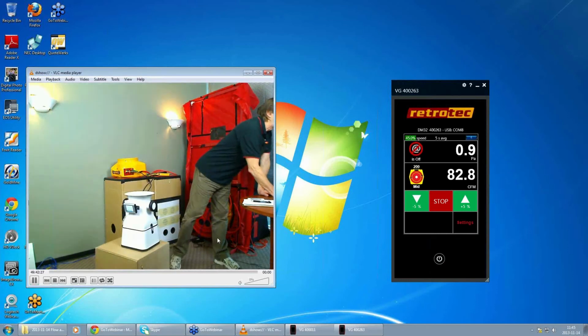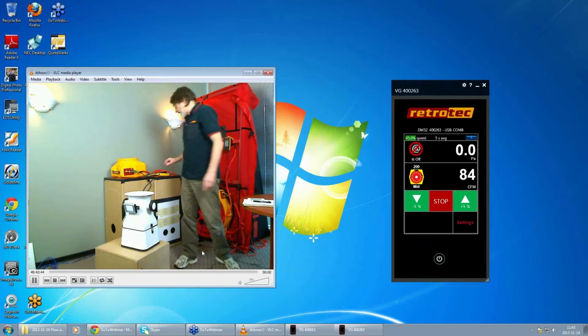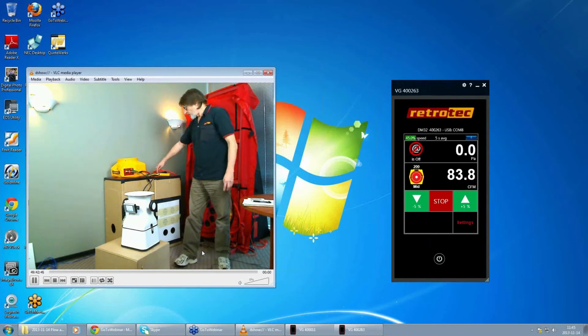Okay, any more questions? The length of tubing making a difference? No, it does not, unless there's a leak in the tube. We've tried as much as 1,000 feet of 16th ID tubing, and we didn't notice any difference at all. The only time that makes a difference is when there's flow through the tube. But when the gauge is hooked up like this and the connections are tight and there's no leakage in the system, the length of the tubing doesn't matter.